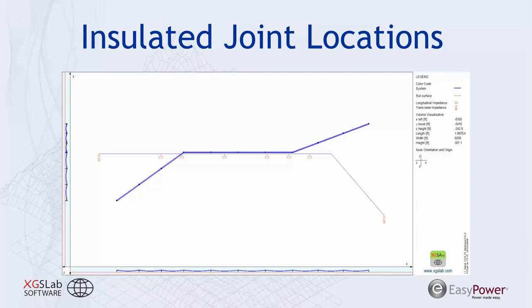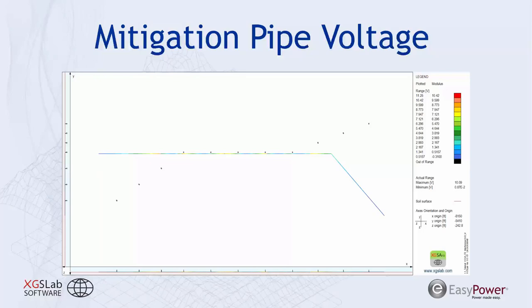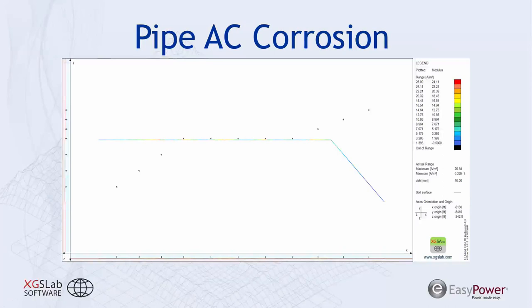So when you incorporate those breaks or those insulated joints in the pipeline, you're reducing the length of exposure for the pipe. And by doing that, we're able to reduce the voltage to less than 12 volts that's induced upon this pipe section. And that reduces our AC corrosion, or our amps per meter squared again, to acceptable limits below that 30 amp per meter squared value.